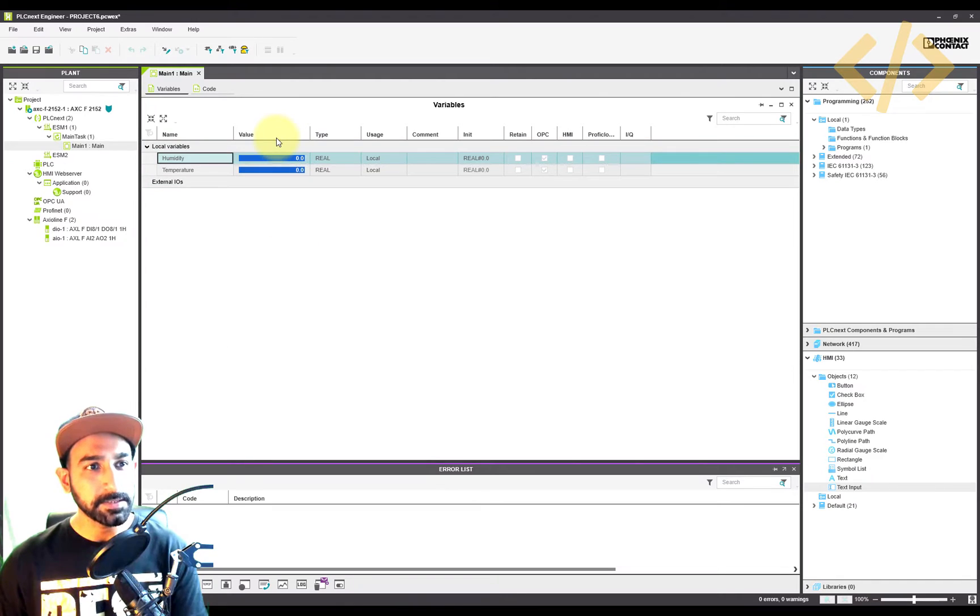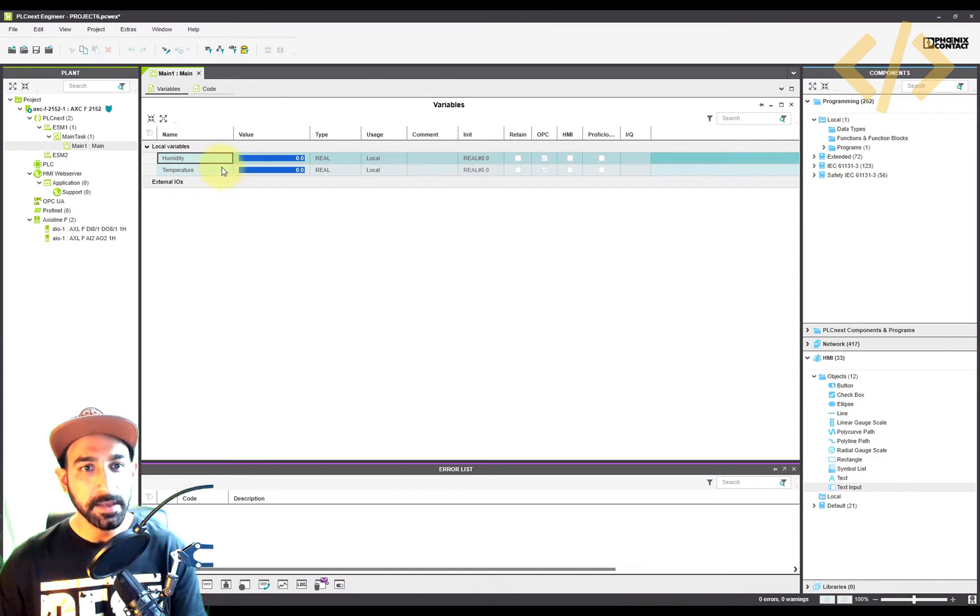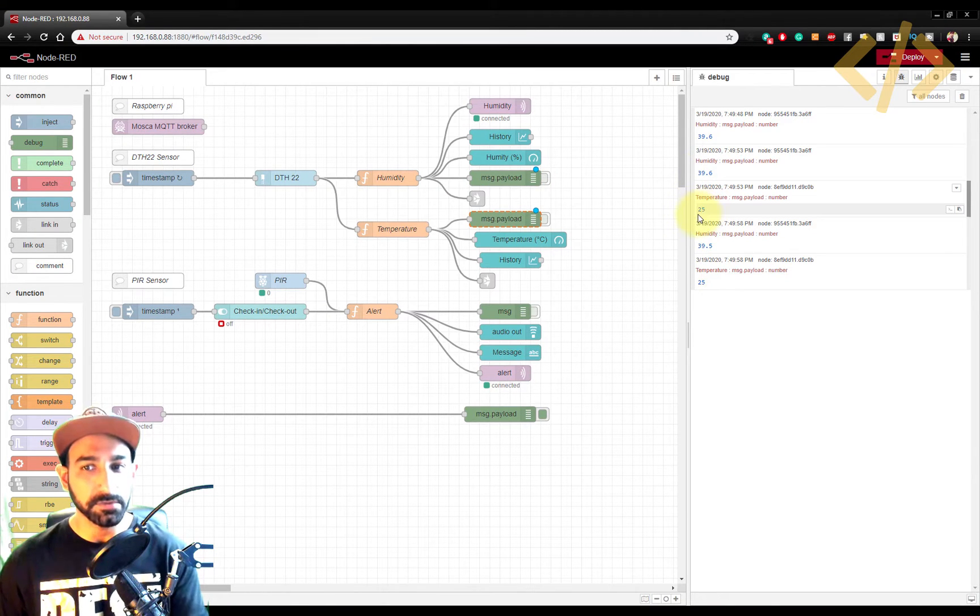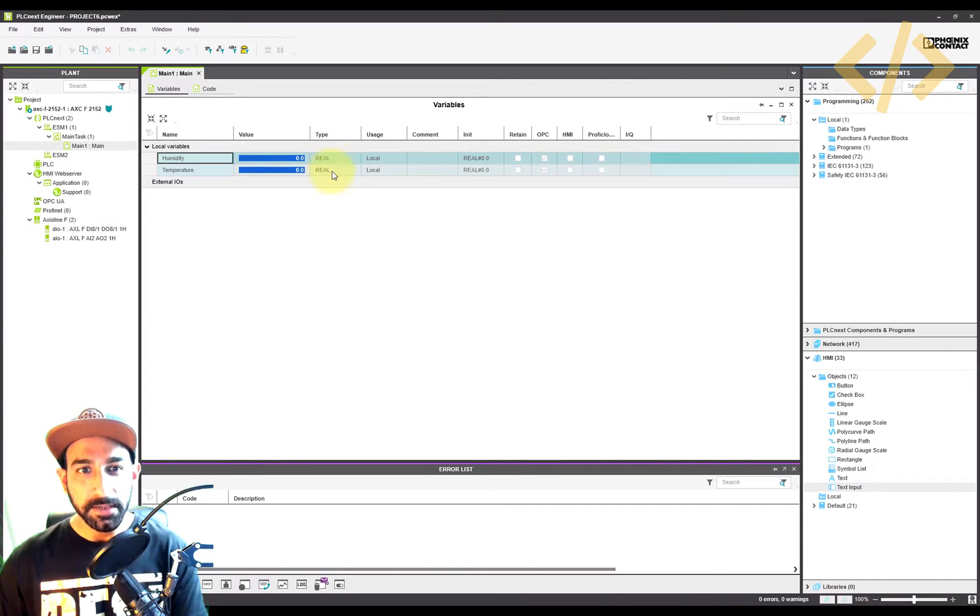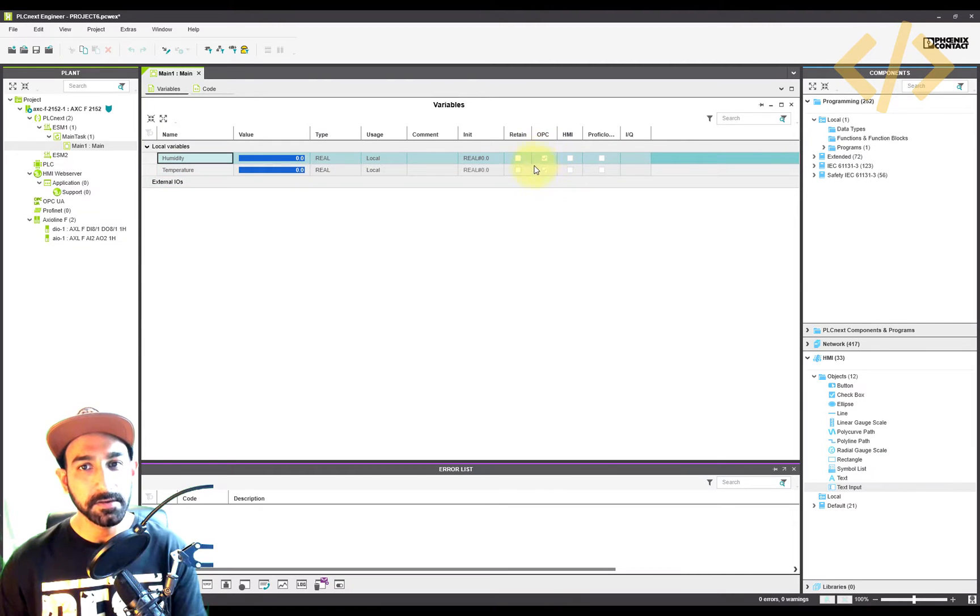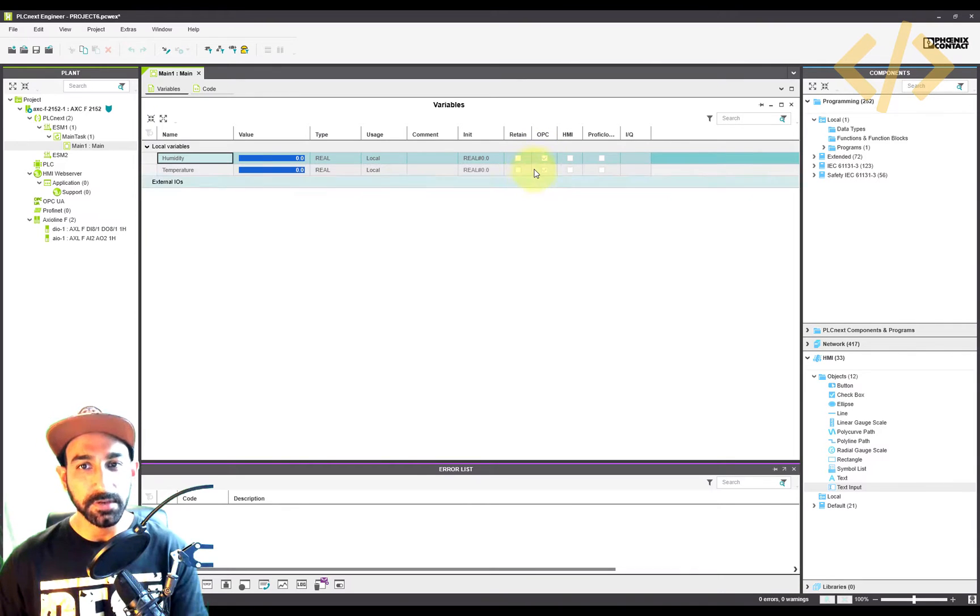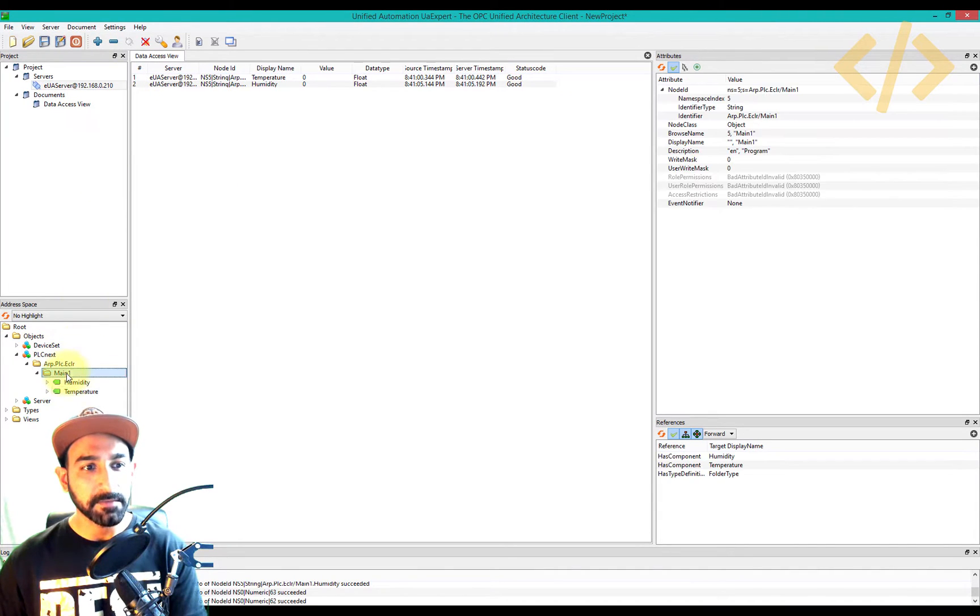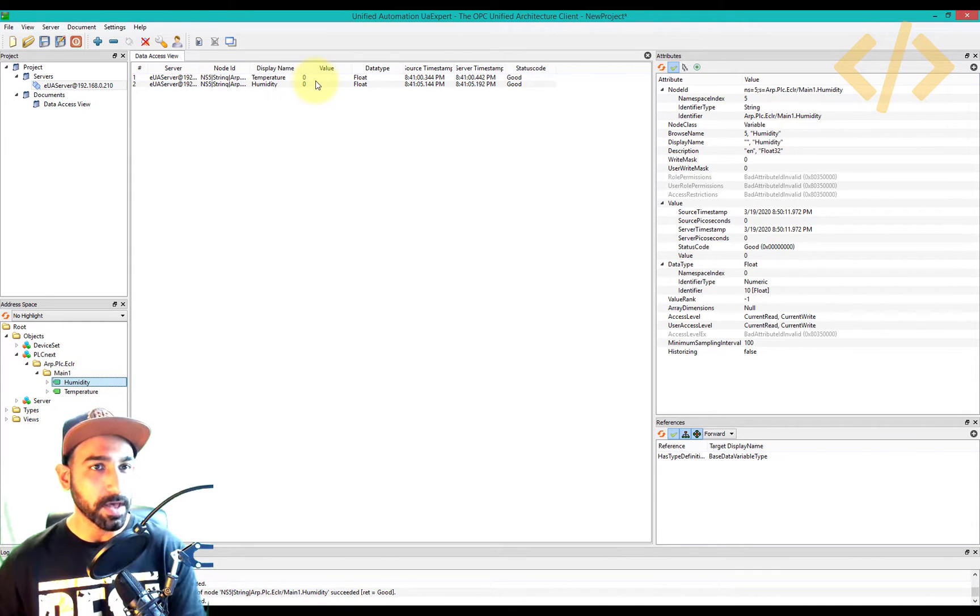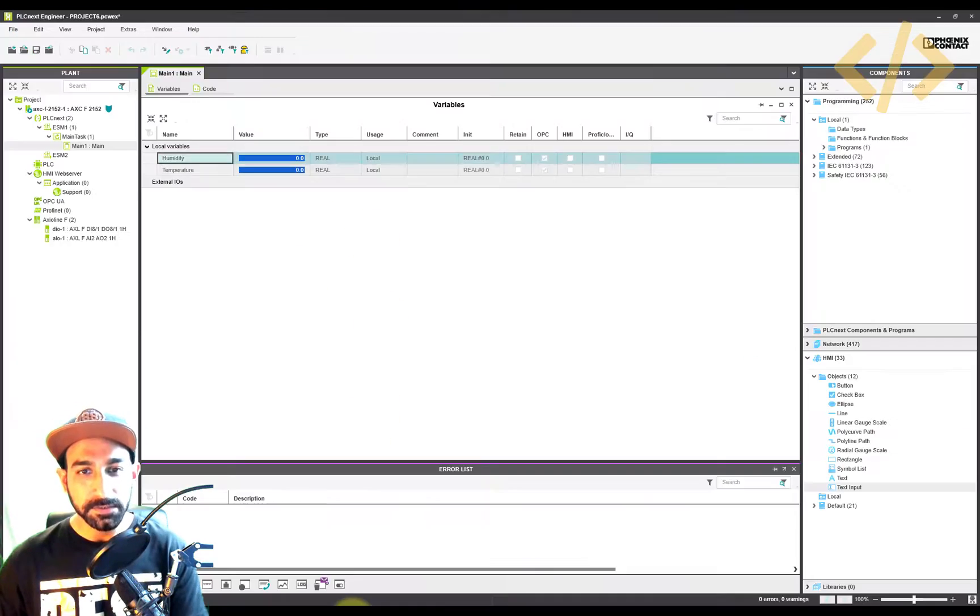These two values we want to push inside the PLC. And the PLC I can show you here. That's my PLC. And in the main logic, I took two variables, which is humidity and temperature, two local variables. And these are type real. I took real because you see these are the real values. Temperature value could also be real. So I took two real local variables and I named it humidity, temperature, and I just ticked OPC so I can rewrite the values of these in the OPC. So let's just verify these two tags in my OPC UA in UA Expert. This is my OPC server and that's my value: humidity and temperature. And you see both are zero, there is no value, there's no connection.